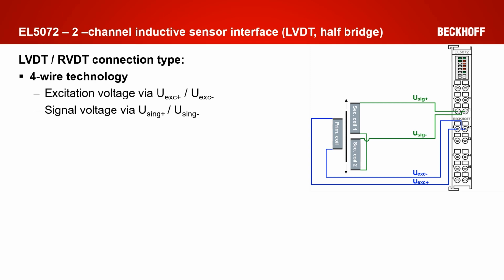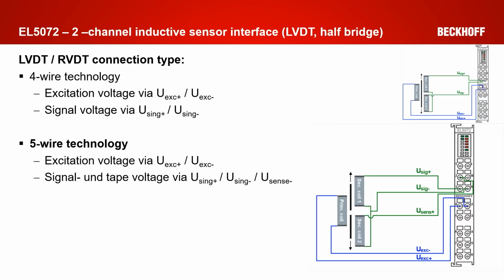The measured output voltage is mainly subject to the dependencies of a nonlinearity of the individual secondary coils, but also fluctuations of the integrated supply, for example, caused by some cable lengths. Furthermore, some sensors offer an additional line, the so-called center tap. This corresponds to a 5-wire connection. The voltage between the signal line and the center tap is measured and put into relation. So we have here a ratiometric measurement. This measurement method offers some advantages and also increases the accuracy.